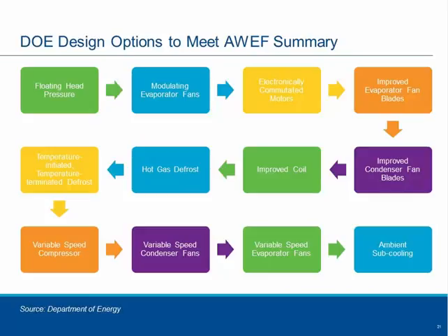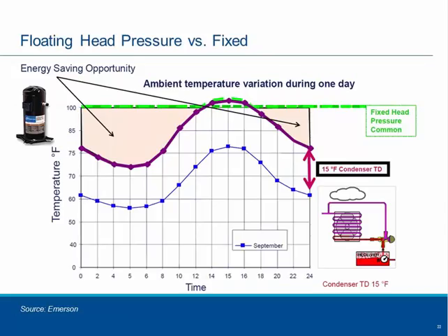Well, part of it has to do with the inherent efficiency of the compressor and being able to move to a common platform for low temp and medium temp. And also the coming on of new refrigerants and how scroll can handle those. But one of the overlooked important things about scroll compressors is the ability to float the head pressure down. Let me explain to you what that means in this chart. I also want to mention that as part of the E360 program, there is a whole webinar that we did in 2013 that's available right now on the Emerson Climate E360 website if you want to learn more about this. This is just one chart from that webinar.